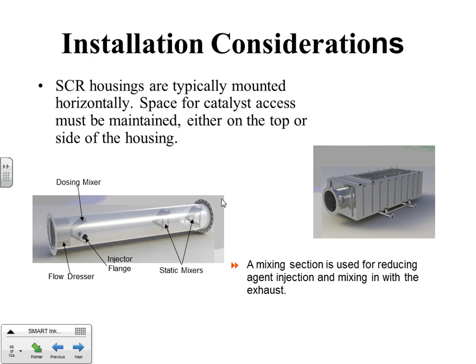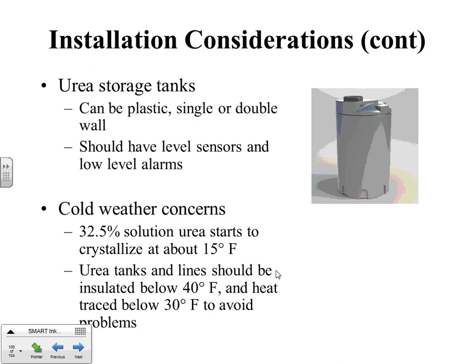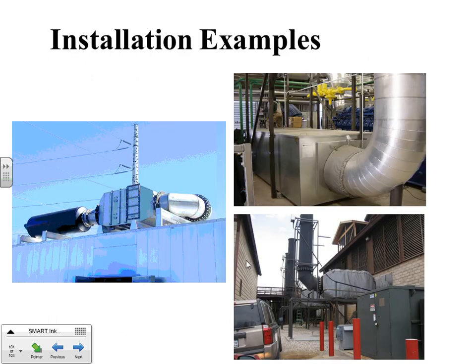Installation considerations. This is some of the equipment, the SCR housing that's going on that unit now. This piece here, this dosing, is the urea coming into this chamber. Exhaust is coming in this way, being injected, and it's going through here and mixes in this section and then goes across the catalyst at the exit. Again, this cold weather concern: a 32.5% solution of urea, it's actually a liquid, starts to crystallize at about 15 degrees. So now we're heat tracing tanks and lines to keep problems with freezing out. Again, a lot more control, a lot more things to be concerned about with your engine.